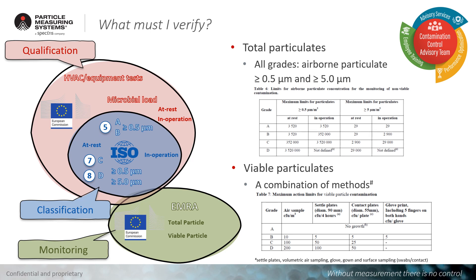Nothing new regarding the way we must monitor. For total particle, we must measure the airborne particulate concentration of both dimensions — 0.5 micron and 5.0 micron — for all grades. Regarding microbial monitoring, the new draft confirmed what we have seen in previous drafts: a combination of settle plates, volumetric air sampling, gloves, gowns, and surface sampling with swabs and/or contact plates.